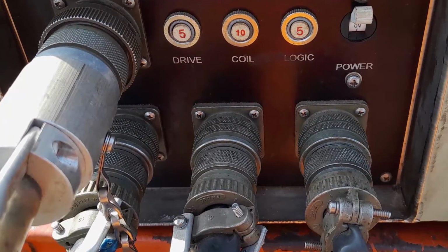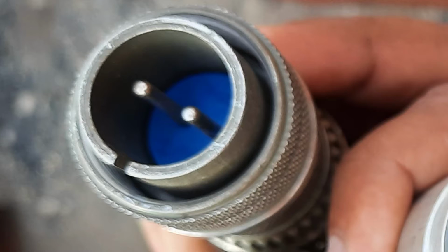The cables. Four types of different cables are needed for the EMI inspection. First is a 3-pin cable that energizes the console with 110 power. A 3-pin power cable is also a male-only cable. One end is male and the other end is the plug point. Next is the coil cable. It is a 2-pin male and female cable. The coil cable transfers the DC power from the console to the EMI DC coil. It's a male and female connection.